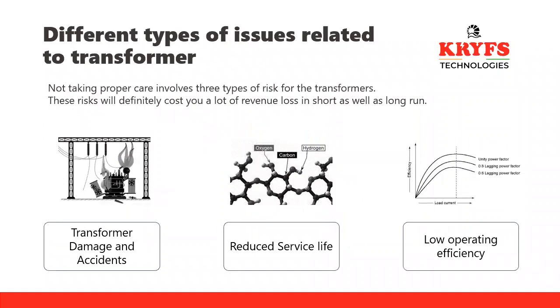Not taking proper care involves 3 types of risks for the transformer. These risks will definitely cost you a lot of revenue in the short as well as the long term. The revenue lost in a transformer can be categorized in 3 forms. One is the transformer getting damaged and accidents happening, meaning some blast or short circuit flash, the transformer getting completely damaged. Second, revenue loss can be through reduced service life. If the transformer is supposed to run for 25 years, it will run only for 5 years. Third is low operational efficiency.